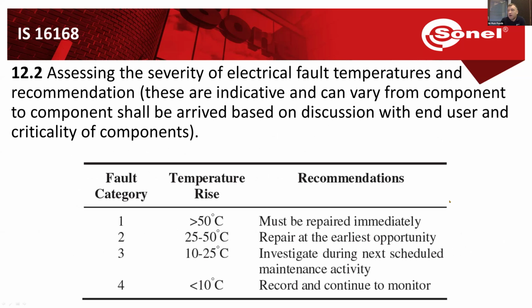Now, how severe are the problems we find? There's a table in the standard that says if the difference from the expected normal condition is below 10 degrees, we just monitor it—nothing unusual. If the difference is between 10 and 25 degrees, we should investigate during the next scheduled maintenance. If it's between 25 and 50 degrees, we need to repair at the earliest opportunity. And if the difference is above 50 degrees, it must be repaired immediately, as it's an emergency situation. These are, of course, recommendations.